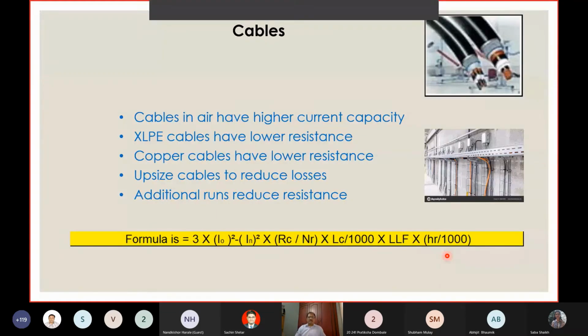So when it comes to cables, Terry has published a formula. The formula is written at the bottom. You can use this formula in an Excel sheet. I'll show you one Excel sheet next for one of the industries where feeder-wise cable losses have been found out, and we have told the customer to either undertake 2 runs or 3 runs of cables or increase the cross section of the cables. Cables are put in the earth, or they are also used in ducts in the air. Current carrying capacities are higher when it is in the air.